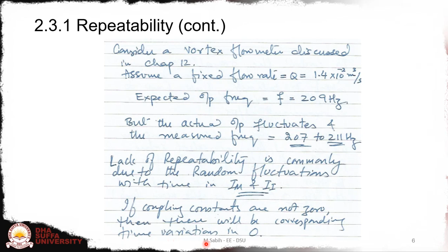Now consider a vortex flow meter, where the fixed flow rate is 1.4 × 10^-2 cubic meter per second, and the expected frequency is 209 hertz. But when we actually look, the fluctuations may be from 207 to 211 hertz. The lack of repeatability is commonly due to random fluctuations with time because of IM and II, the modifying input and the interfering input from the environment. If the coupling constants, for example Km and Ki, are not zero, then there will be corresponding time variations in the output.